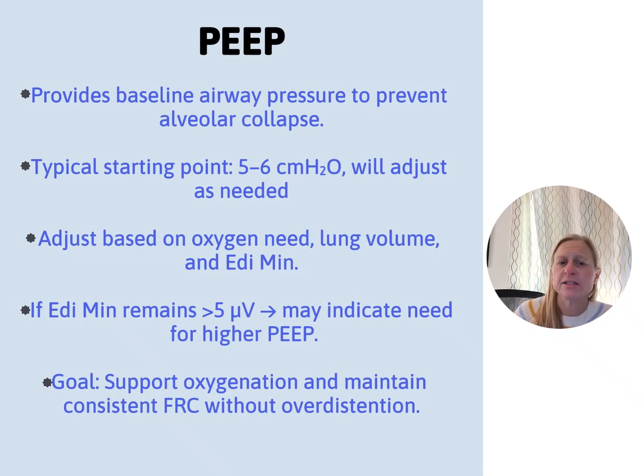On NAVA, similar settings to start, 5 to 6, adjust as needed. As you saw in the last one, the baby was on 9. You can have that moving around. If the Edi Min remains greater than 5, that might tell you need to increase your PEEP. So that's a great thing to know. And we really have to think about our functional residual capacity and what we want here, because we need to have a little left over. So think of that as you go through.